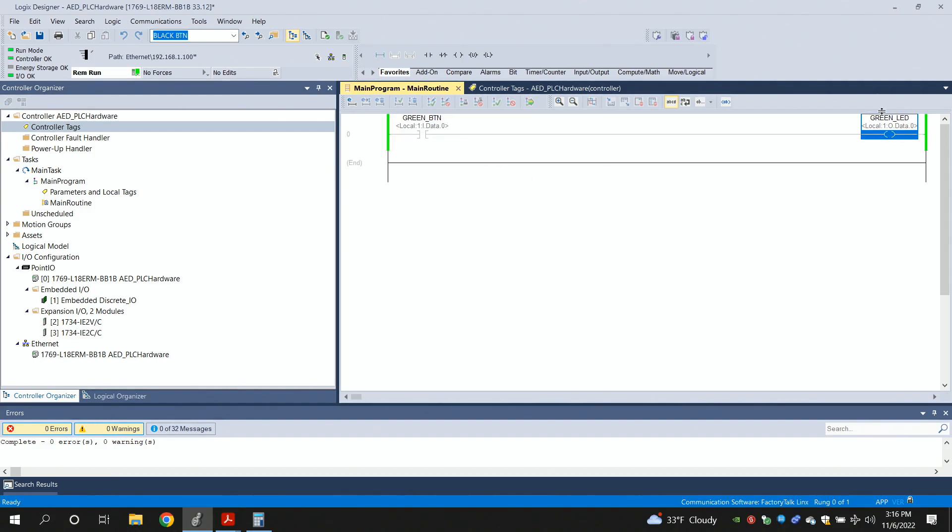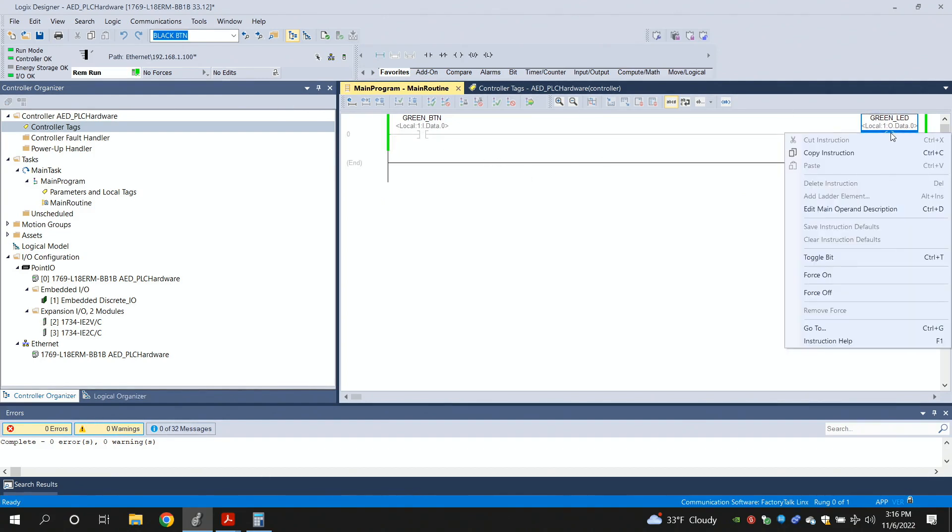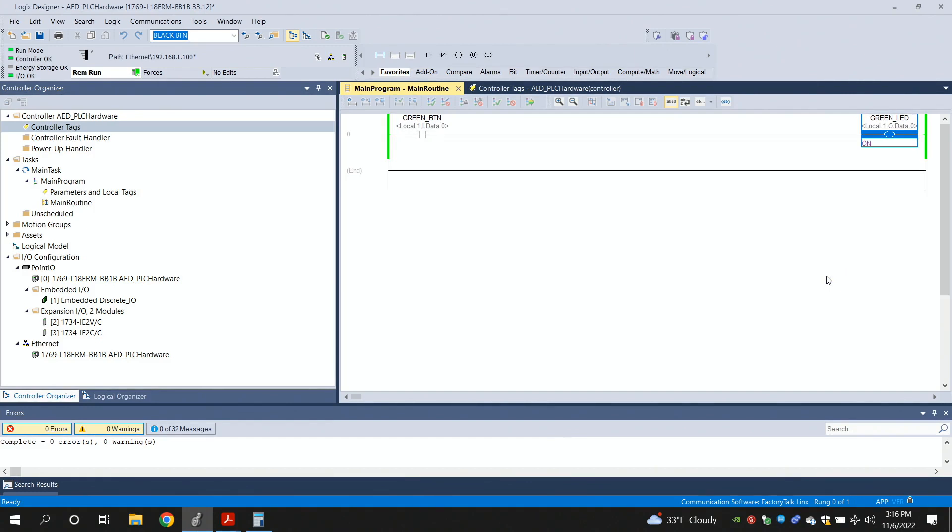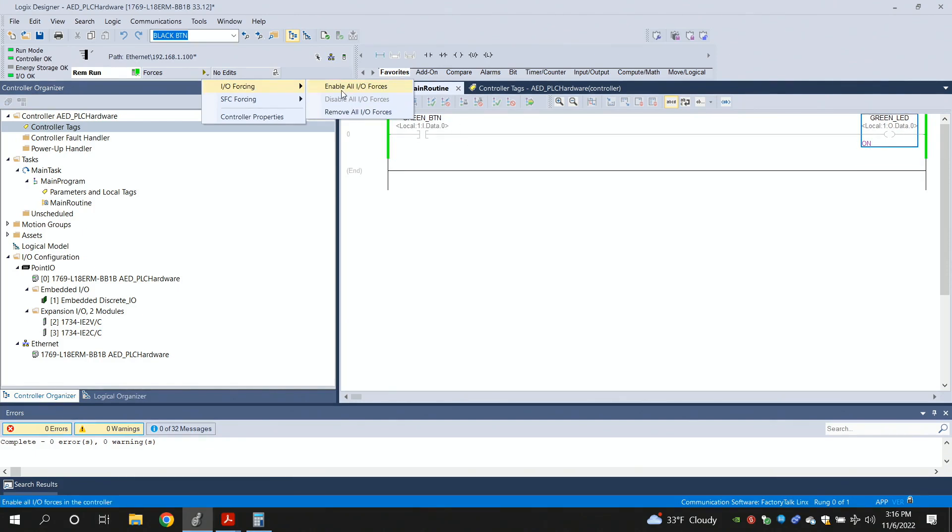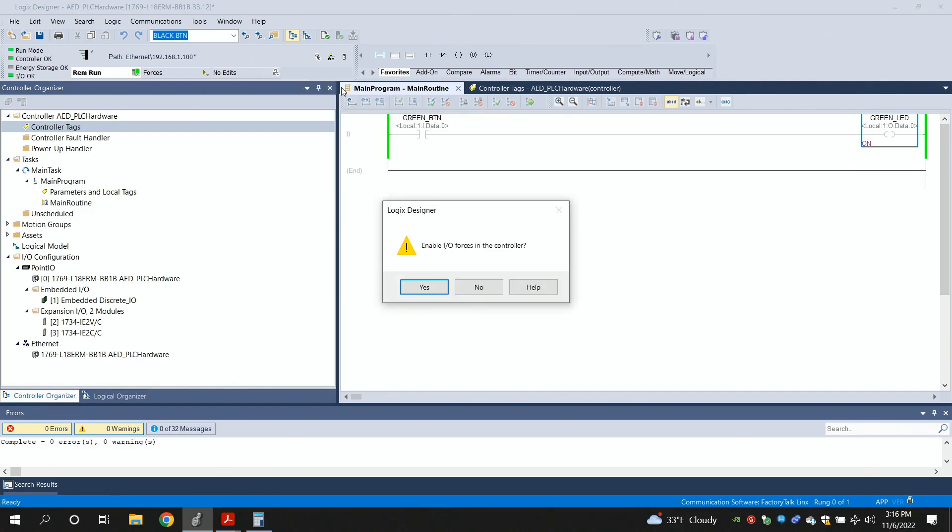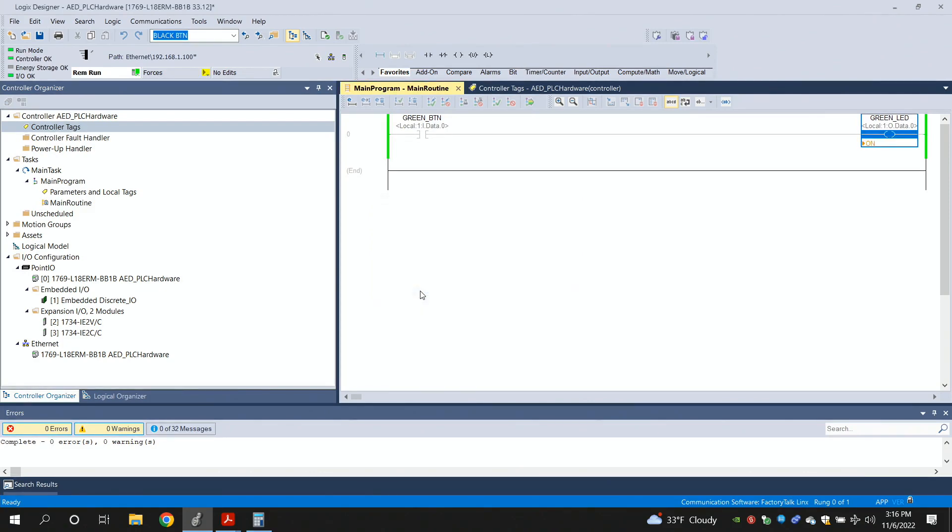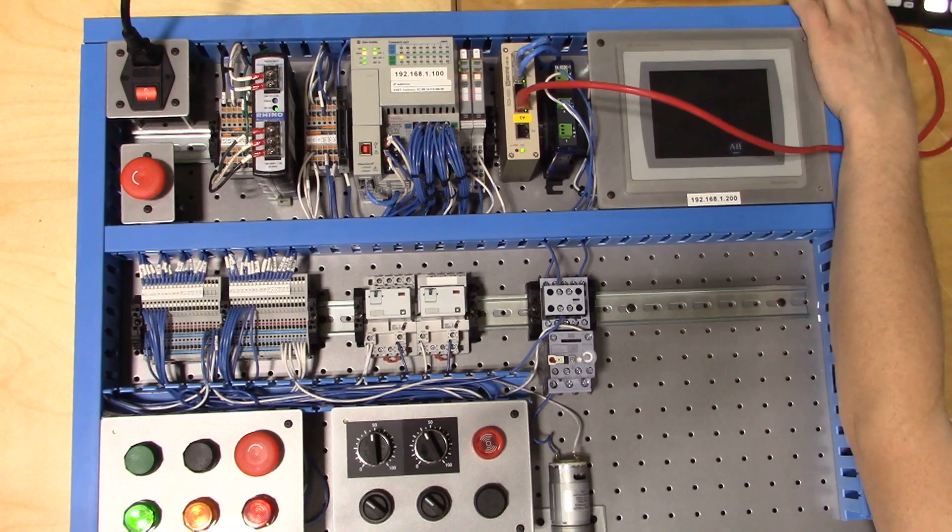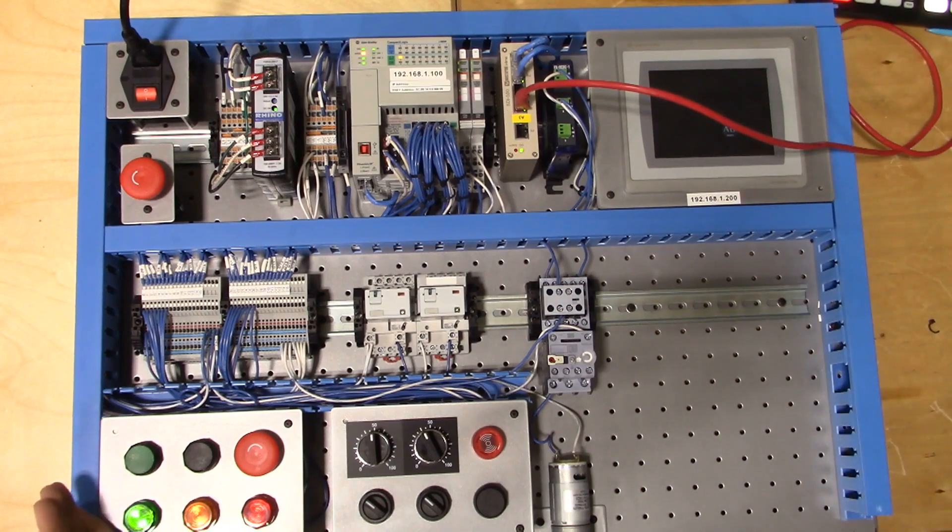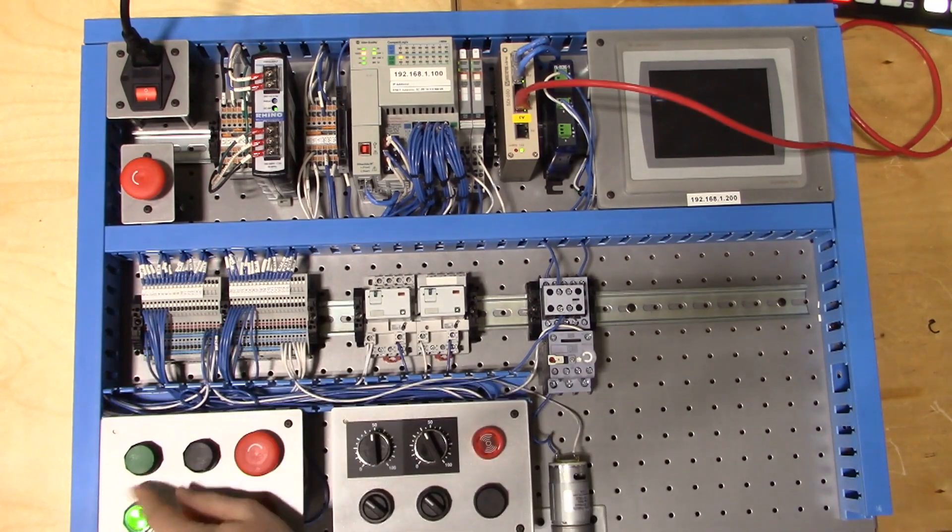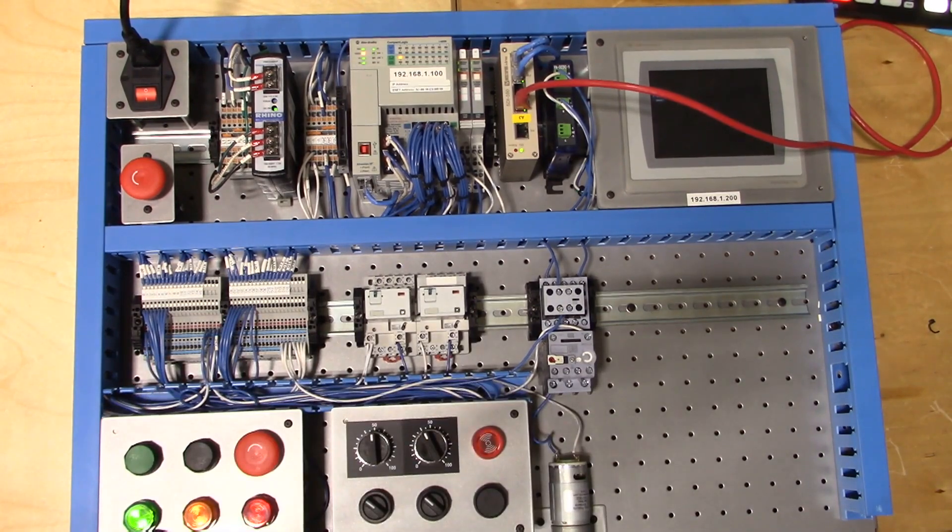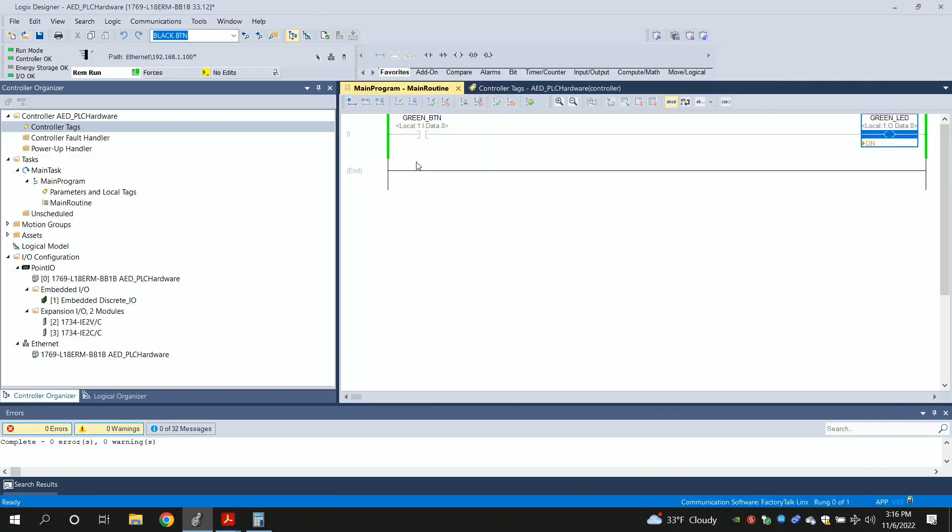Right now you can see the green LED is in its off state over here. And if I right click on that element, I can choose force on. And right now this forces shows up over here. IO forcing and I can click on enable all forces. You can see there's a little on that showed up in purple over here. This bit is being forced on. And if I click this enable all IO forces, it says do you really want to do that? Because here's the thing. Stuff is going to start up. I'm going to click yes. And when I look at the PLC output over here, this LED in that bottom corner there is actually turned on now. And it's not on because of the programs calling it on. I'm forcing it on through the software.